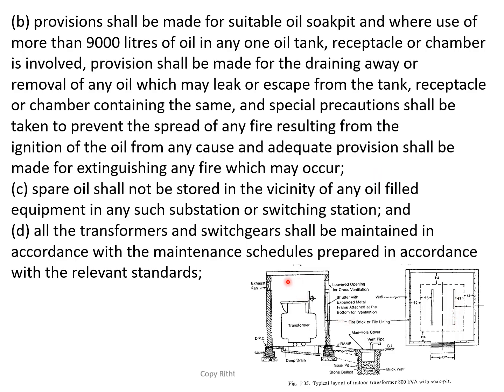The soak pit is shown here. This is the transformer room, and from the transformer room, through sloped construction, a soak pit is provided in which oil will travel. This shows the two railings of the transformer in the plan. This is the elevation. Spare oil shall not be stored in the vicinity of any oil-filled equipment in any such substation or switching station, and all the transformers and switchgear shall be maintained in accordance with the maintenance schedule prescribed in the relevant standard.